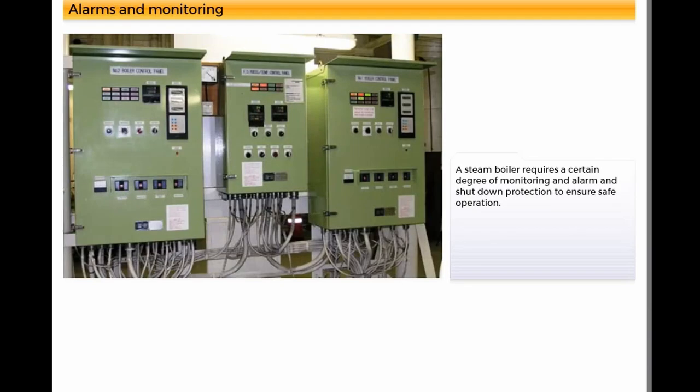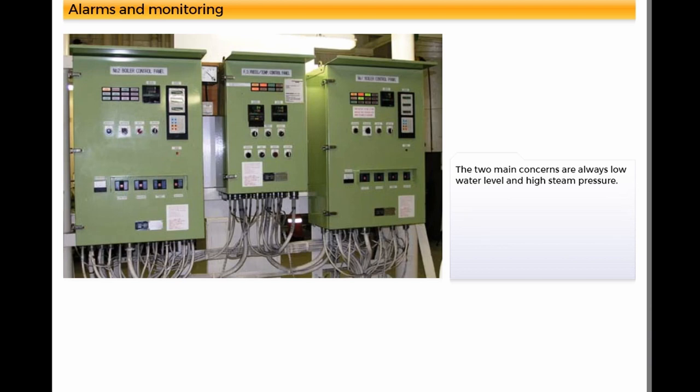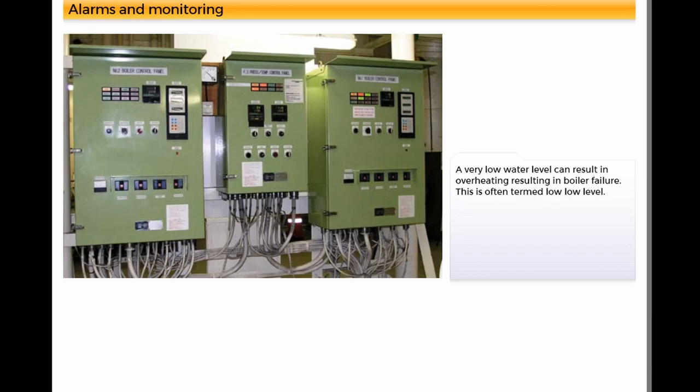A steam boiler requires a certain degree of monitoring and alarm and shutdown protection to ensure safe operation. The two main concerns are always low water level and high steam pressure. A very low water level can result in overheating, resulting in boiler failure. This is often termed low low level.